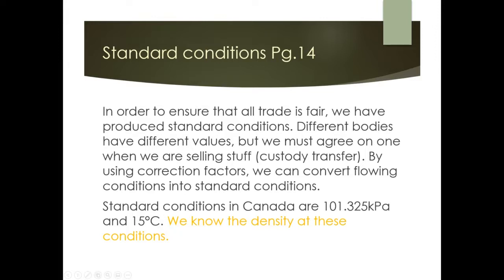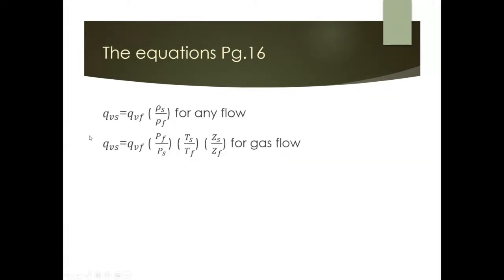The formula for volumetric flow at standard conditions (indicated by subscript 's') is: flowing conditions × (density at standard / density at flowing). For gases, additional variables for temperature and compressibility must be included, because gas has those characteristics that must be accounted for — unlike solids or liquids.